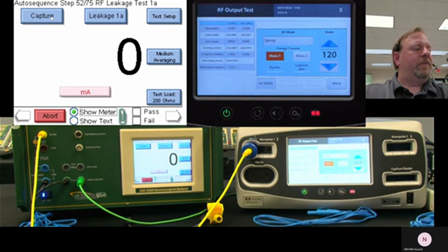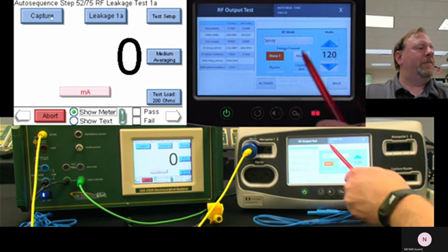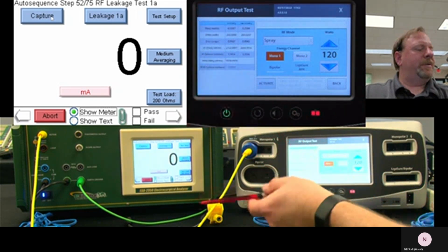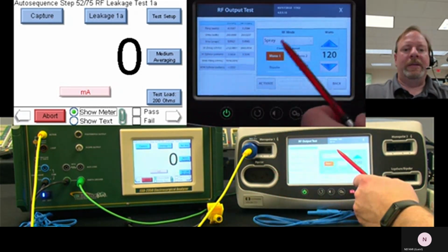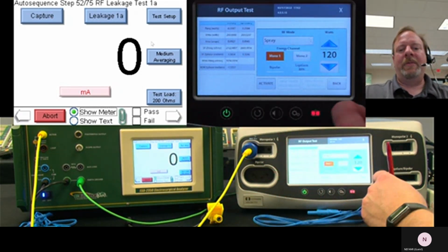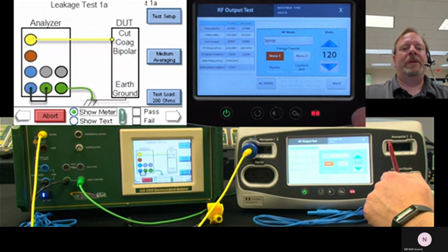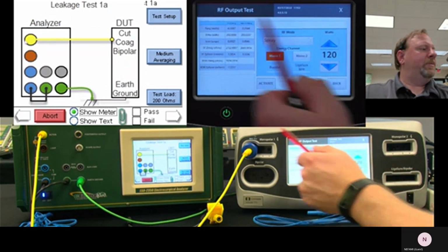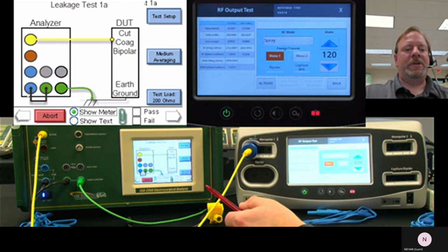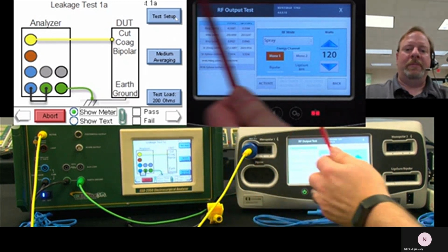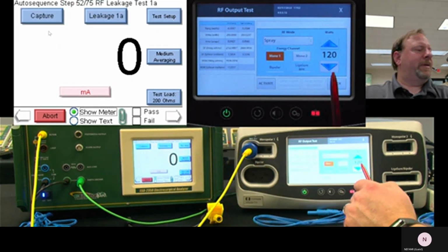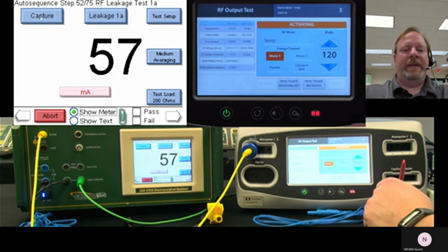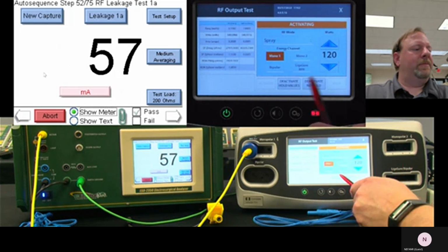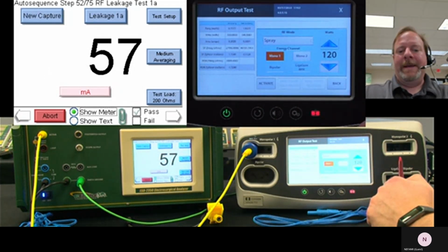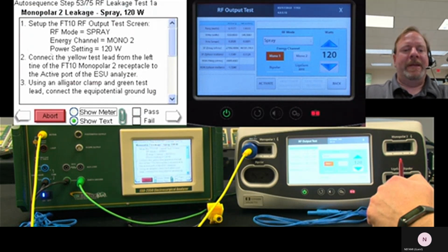So we go in here, maximum output, monopolar 1. We're measuring the earth ground. You can see here, leakage 1A. We can also look at the test setup, and it says yellow, active, jumper to ground. Good. Followed my instructions properly. I hit activate, and that's either good or bad. In this case, it's good.